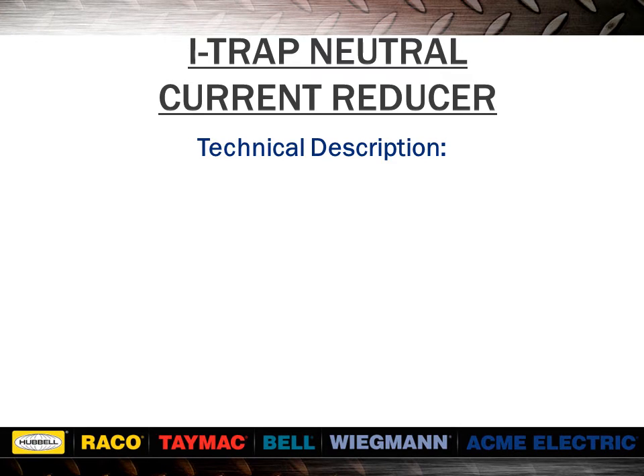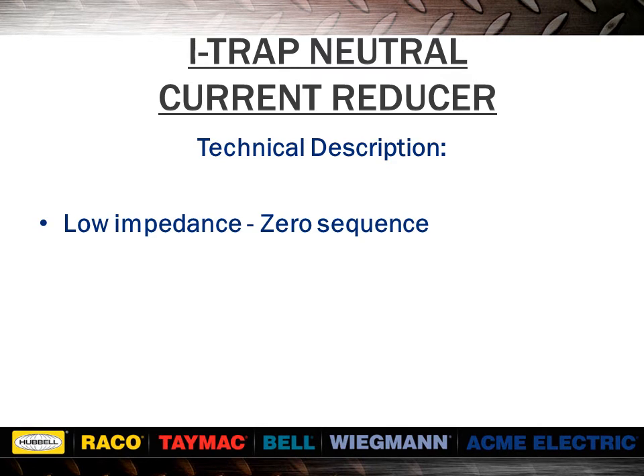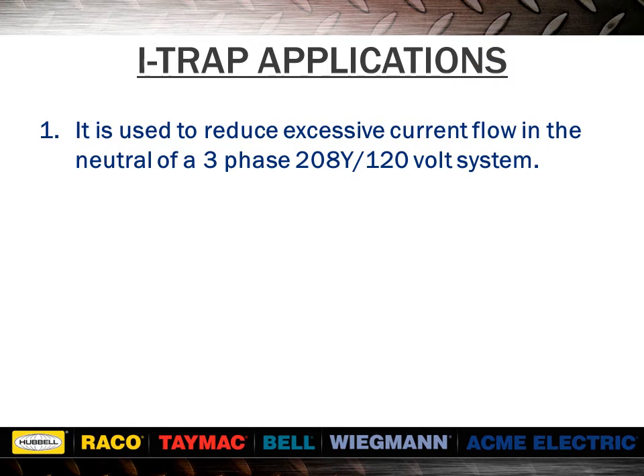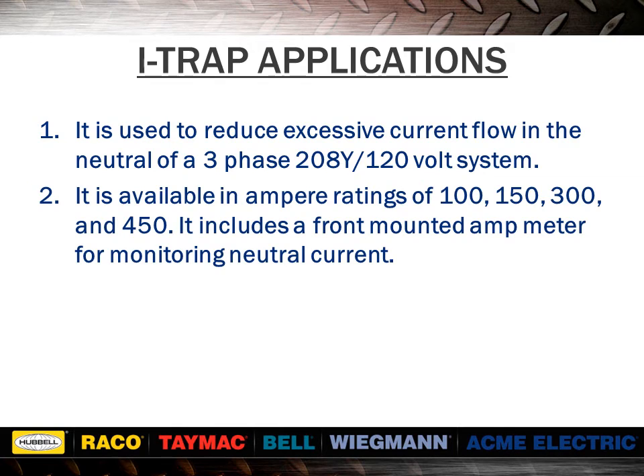Next, we'll discuss the I-TRAP neutral current reducer. The technical description of an I-TRAP neutral current reducer is that it is a low impedance, zero sequence, auto zigzag transformer. It is used to reduce excessive current flow in the neutral of a three-phase 208Y/120-volt system. It is available in amp ratings of 100, 150, 300, and 450.